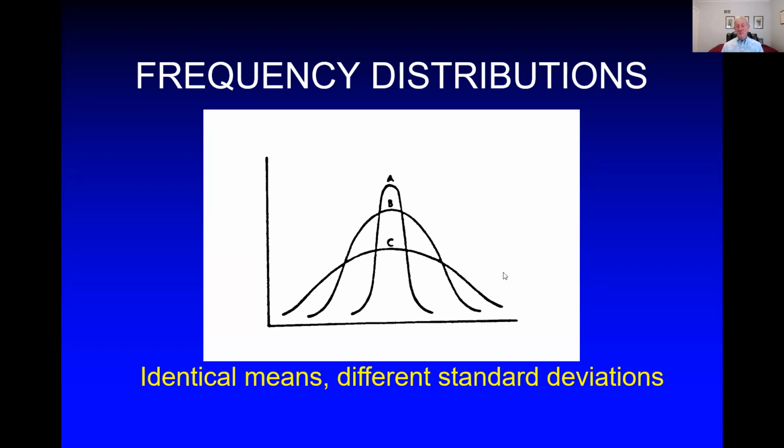I don't think so. You would want the smallest standard deviation you could get. Let me give you an example of numbers where you would generate a curve like this. Let's say you have a dose calibrator source that's 10 millicuries, and you read it 3 times, and you have values of 9.5, 10, and 10.5. That might give you curve A, where you have a small deviation.